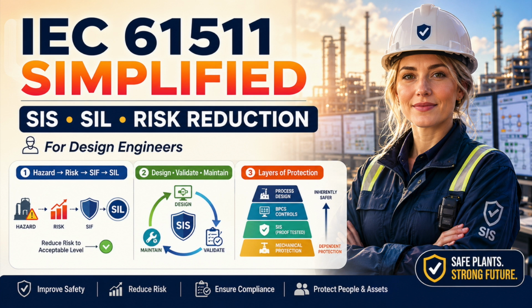The sensor, logic solver, and final element form the visible chain, but the process dynamics decide whether the chain is effective. A trip set point is not just a number. The process continues to move after the trip condition is detected. There is sensor response time, signal transmission time, logic execution time, output actuation time, solenoid response, actuator movement, valve travel, process deceleration, pressure accumulation, thermal inertia, reaction continuation. If the trip is set too close to the maximum safe process limit, the function may act exactly as designed and still act too late. Reliability does not compensate for poor process understanding.